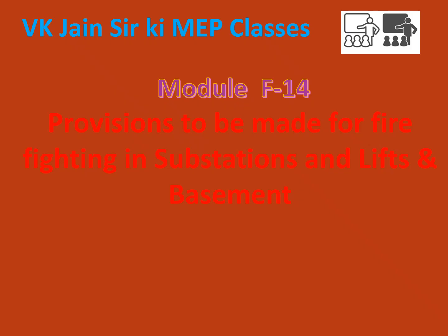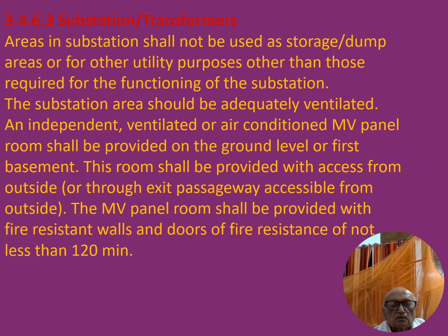In this current series, we shall be discussing provisions to be made for firefighting in substations, lifts and basement. Friends, we will discuss the firefighting provisions to be made in substation, especially in fire transformer rooms. Areas in the substation shall not be used as storage or dump areas or for other utility purposes other than those required for functioning of a substation.